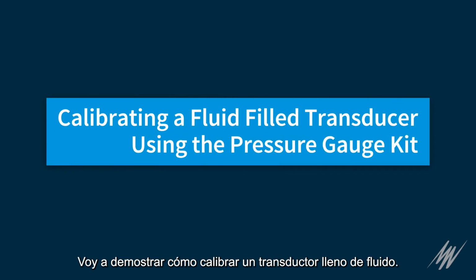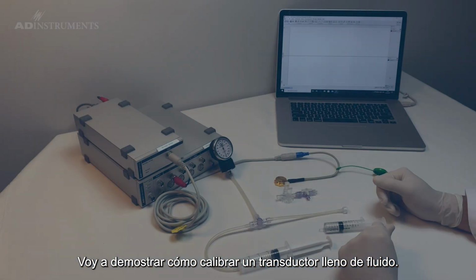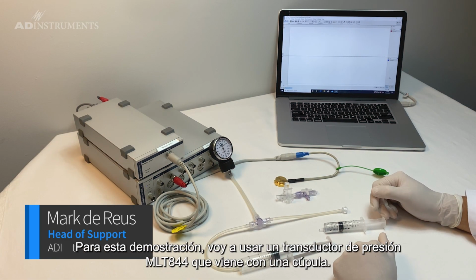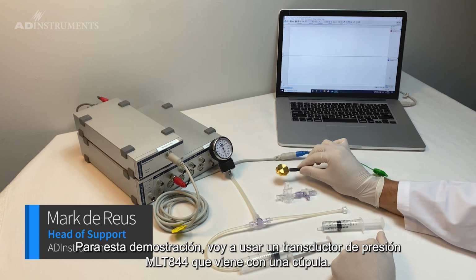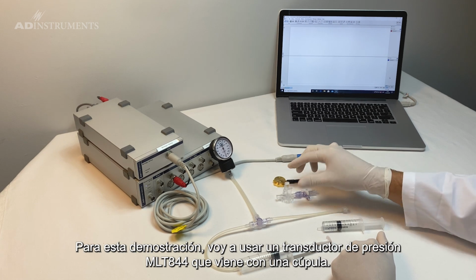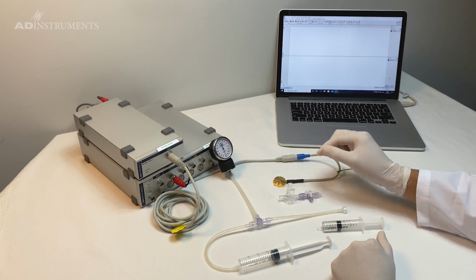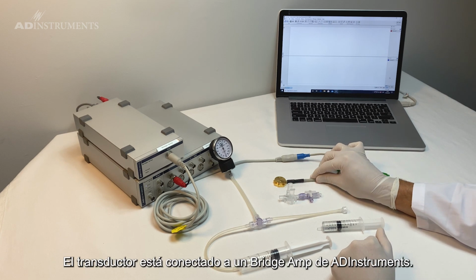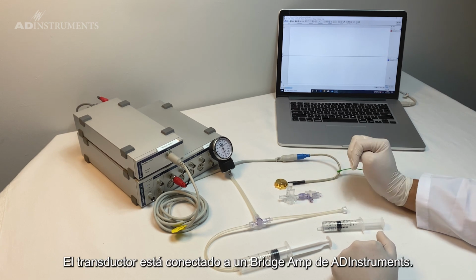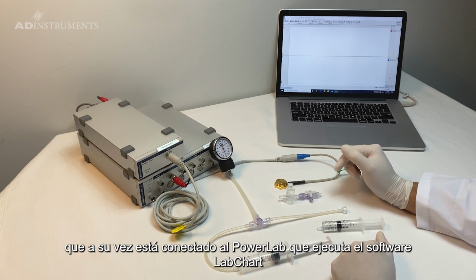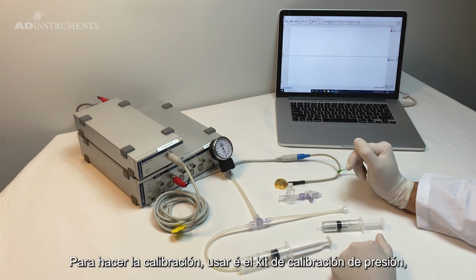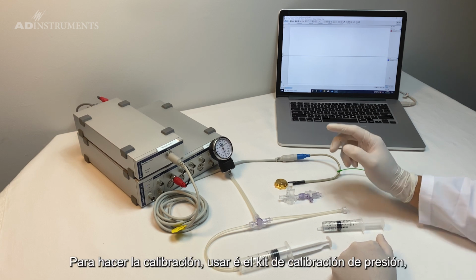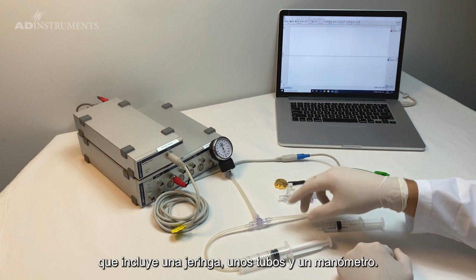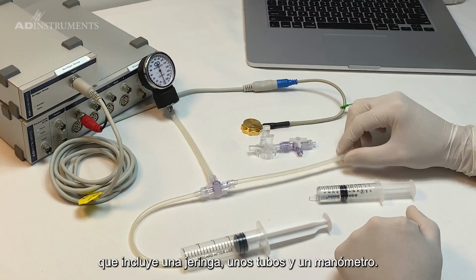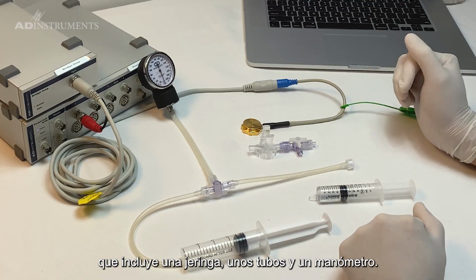I'm going to demonstrate how to calibrate a fluid-filled transducer. For this demonstration I'm going to use an MLT 844 pressure transducer which comes with a dome. The transducer is connected to an ADInstruments bridge amp, which is in turn connected to the PowerLab, which is running LabChart software. To do the calibration I'll be using the pressure gauge kit, which comes with a syringe, some tubing and a manometer dial.